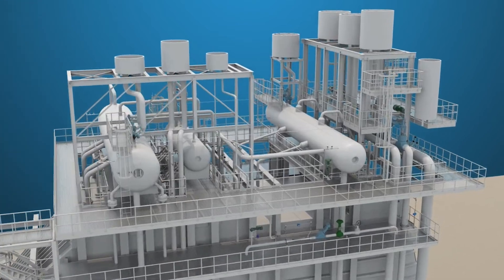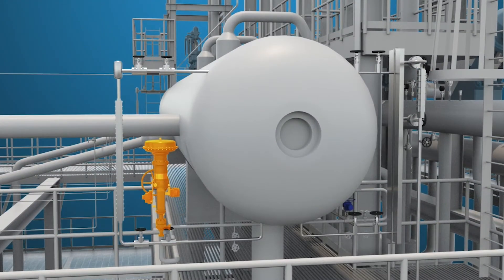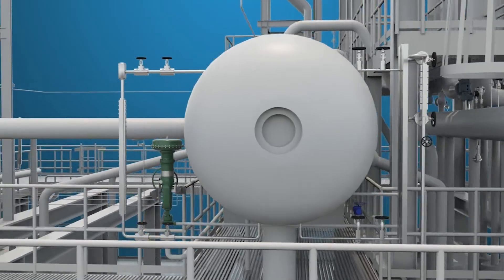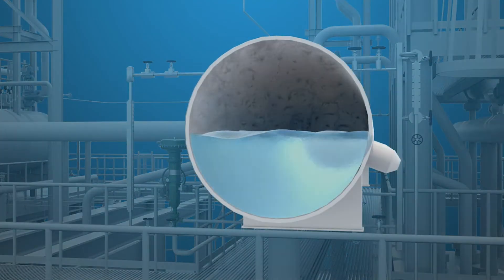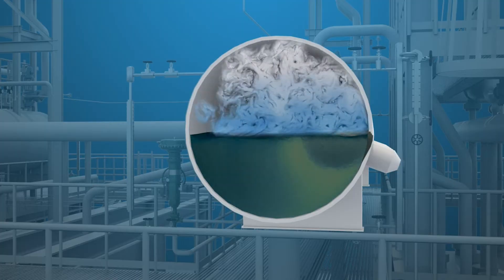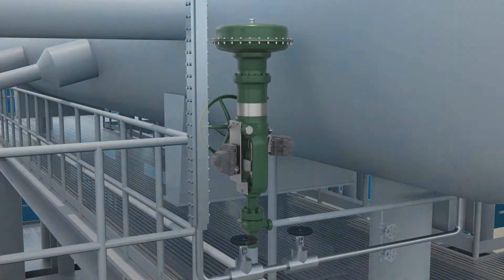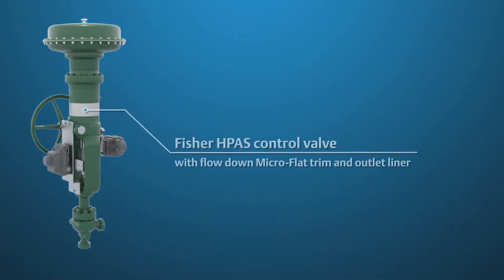As part of maintaining proper water chemistry in the HRSG, chemicals are added to control parameters such as pH, dissolved O2, and others. As water turns to steam, these chemicals drop out, stay in the water, and can reach undesirable levels. The purpose of the continuous blowdown valve is to remove those impurities from the system.